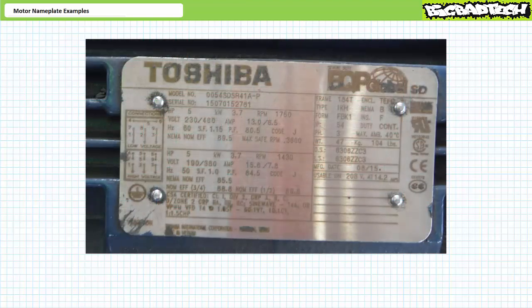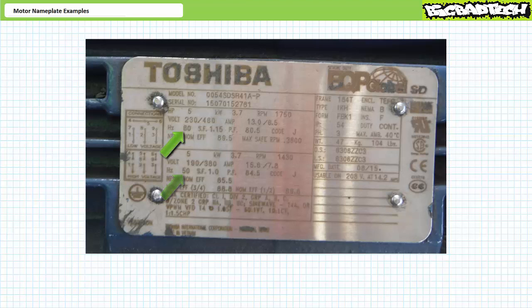Alright, that wasn't too hard. Let's try another example at a faster pace. This nameplate might seem a little blurry — because it really is blurry. Get used to it. Sometimes nameplates are blurry, dirty, faded, or someone painted over them. You should still be able to make sense of most of the data and use your understanding of electrical and mechanical properties to confirm your results. You'll immediately note this is a dual voltage motor that can operate at both 50 and 60 Hz. Let's restrict our analysis to the 60 Hz configuration.